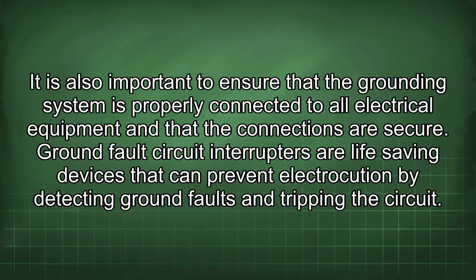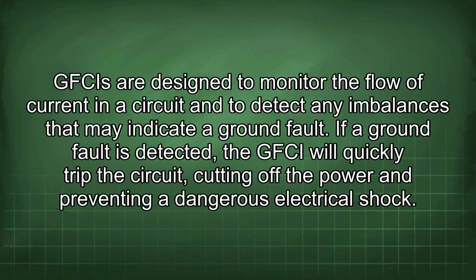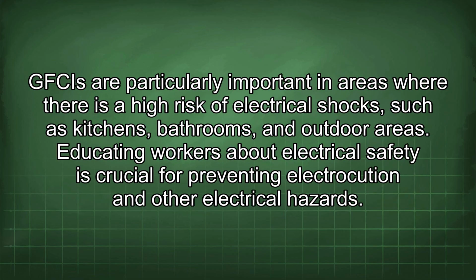Ground fault circuit interrupters are life-saving devices that can prevent electrocution by detecting ground faults and tripping the circuit. GFCIs are designed to monitor the flow of current in a circuit and to detect any imbalances that may indicate a ground fault. If a ground fault is detected, the GFCI will quickly trip the circuit, cutting off the power and preventing a dangerous electrical shock. GFCIs are particularly important in areas where there is a high risk of electrical shocks, such as kitchens, bathrooms, and outdoor areas.